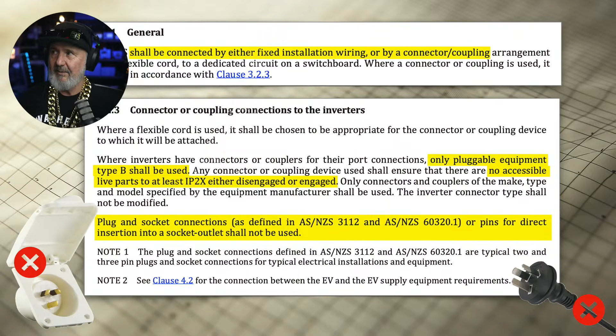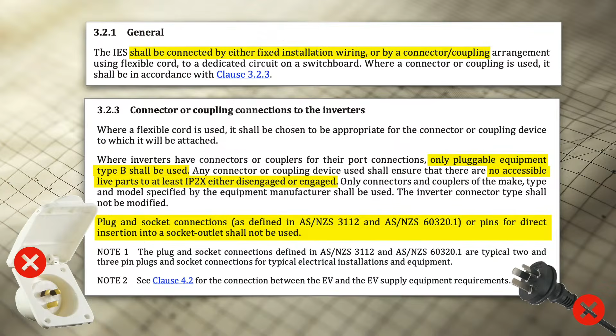This also means that, let's have a look, I'll just come back to this, get my face out of the way for a second. There should be no accessible live parts to at least IP2X when engaging or disengaging. Now, what does that mean? Well, even though you've got a male plug which has the grid supply on the other end of it, even if you try and touch the pins, you can't, because they're shrouded to IP2X. That's a standard test finger. So they're recessed. Now, there have been some failures of this compliance, and I think I've got a picture of one. Where are we? That's not it. There we go, that one there. This is an inspector just pointing out that you can actually touch the pins on this connector with your finger. And so even though it does have a locking mechanism once it's installed, it's still dangerous when it's not connected. So that's not permitted.